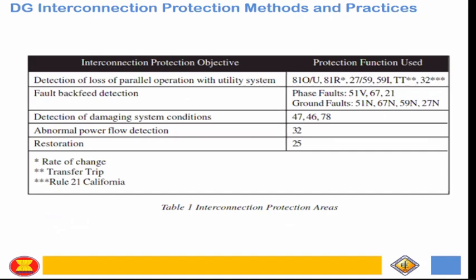Okay. Per standard, these are the protection functions usually used for interconnection protection. We have under/over frequency, then 27 and 59, the under/over voltage, then the instantaneous overvoltage, and the transfer tripping. The objective is detection of loss of parallel operation with the utility. The problem, as I mentioned, is loss of parallel to the utility. There are power quality issues, with variations of frequency and voltage, and there is a limit, so our protection is coordinated with the limits under the Philippine Distribution Code.